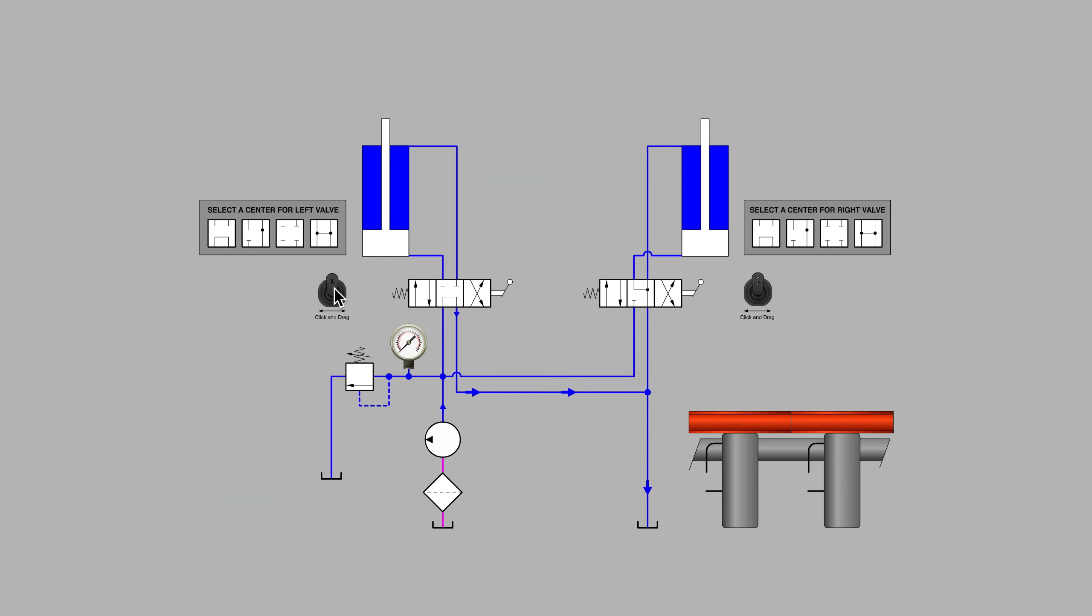When I move the valve on the left into the extend position, will the left cylinder rise? Aha. Yes, it does. The left cylinder rises because when we go into the extend position, we find out that the pumps flow is blocked over here at the right hand valve. And so the only path for the pumps flow at that moment is into the cylinder to extend it. So that seems to be working nicely.